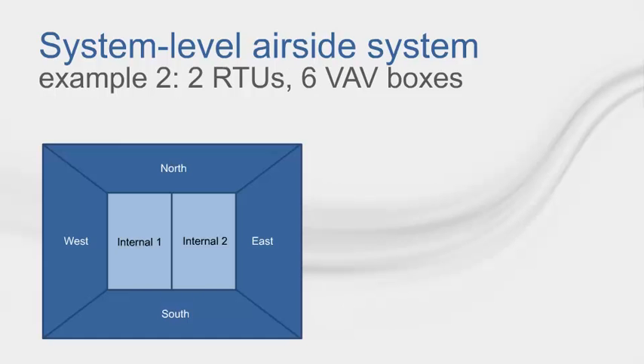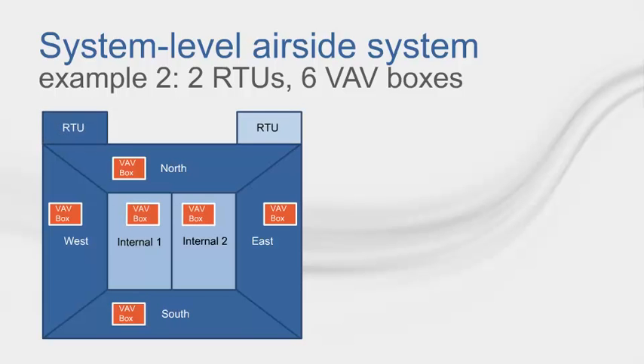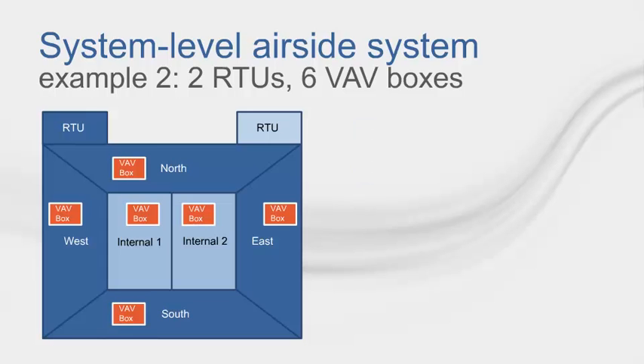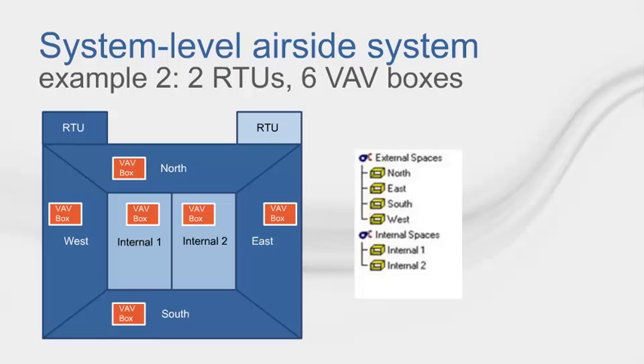In this next example, we have two systems — still six rooms, but now two separate plenum spaces. All the rooms still get their own VAV boxes, but the internal spaces share their own plenum, and the external spaces share their own plenum. In TRACE, this looks like this. Remember, the number of systems you have dictates the number of plenum spaces you have in your building.